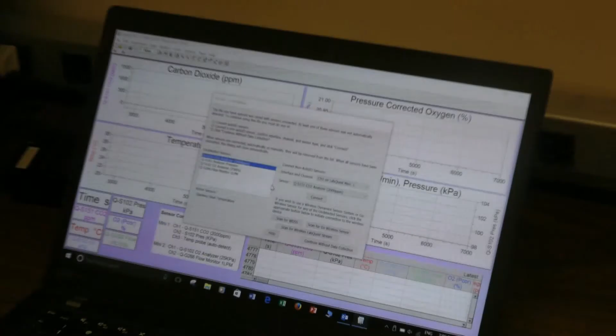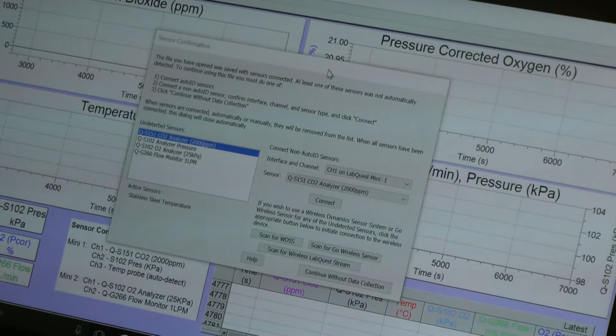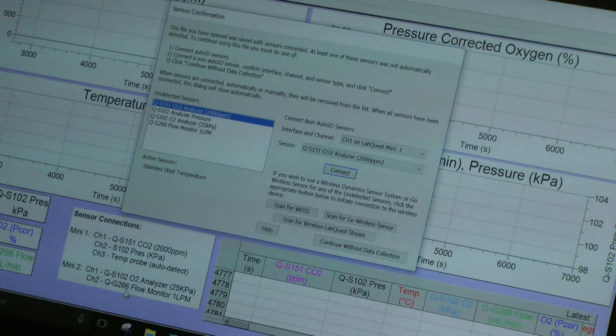The first thing you will see is a sensor confirmation window that shows up, and this is when you have to connect all your sensors. The order of connecting the sensors to appropriate channels is actually shown in this little window here. Mini 1 represents the data interface 1. Channel 1, you should have your CO2 analyzer, S151. Channel 2, you should have pressure from the oxygen sensor connected. Channel 3 has the temperature probe. The probe is auto-detected, so you do not need to connect it manually. And on Mini 2, the second interface, in channel 1, you have QS102, the oxygen sensor of the analyzer. And in channel 2, you have the flow monitor, QG266.